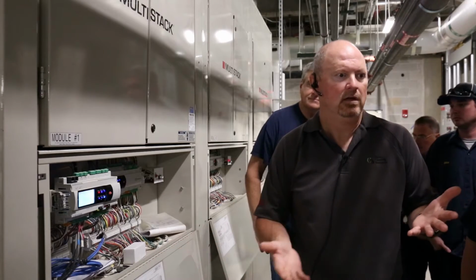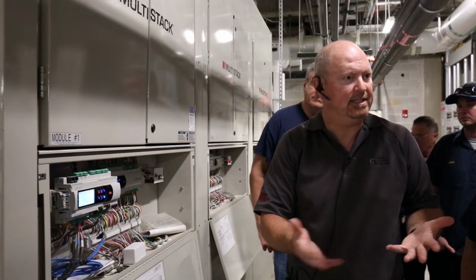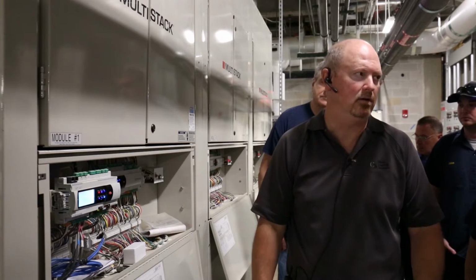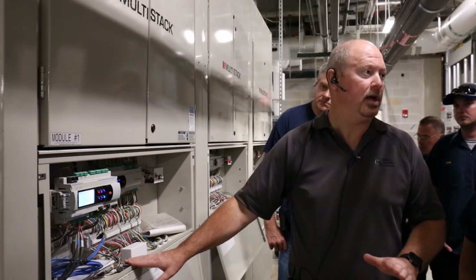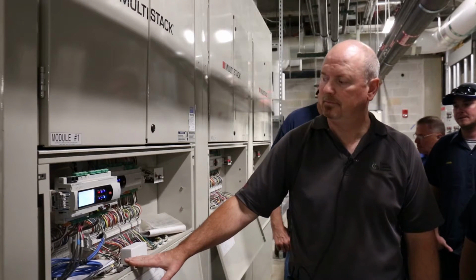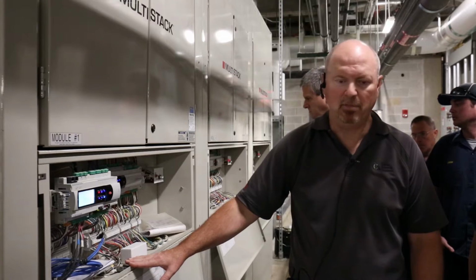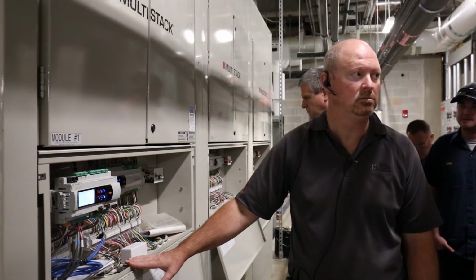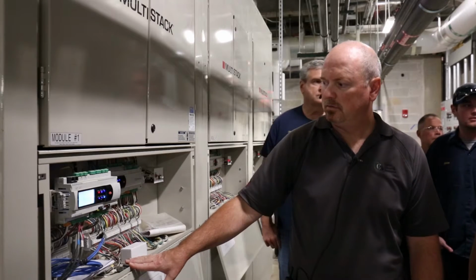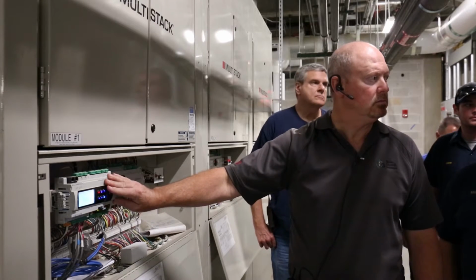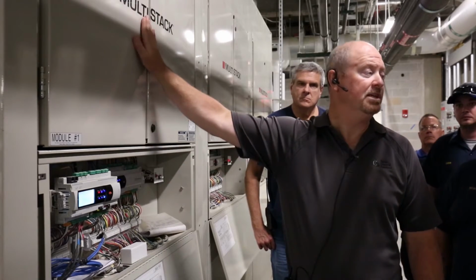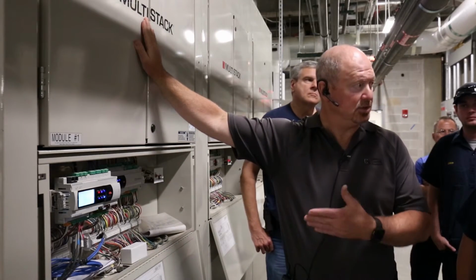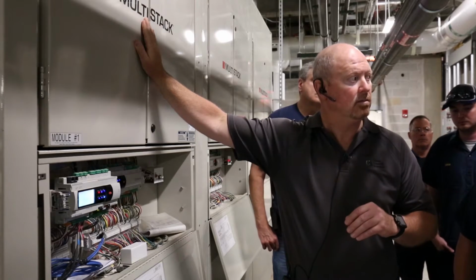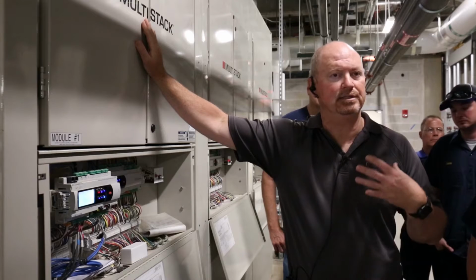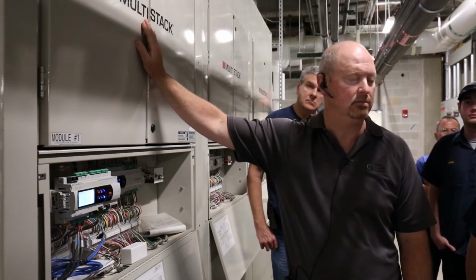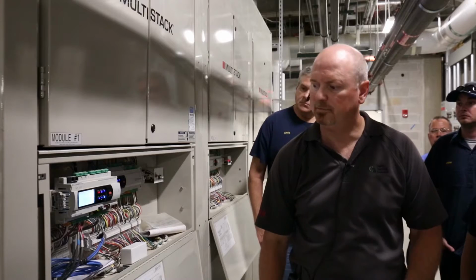Sometimes you have a crossover problem and it just needs to be reset every so often, but that's usually what we have with most of the chillers. So once they get the bugs worked out, then that becomes very minimal. I'm going to go over here and see if we can get flow going so we can clear that along. Well, we're going to have to reset. Oh, it's flowing because we still have modules running now. Yeah. Once it happens, it trips. We need to show them how to reset that switch. Right. Yep. So, okay.